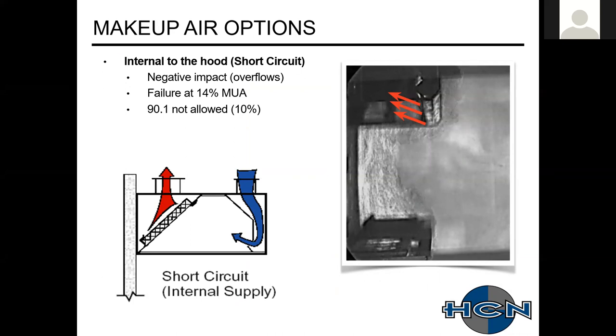The problem with this is, in the way the IMC and the code is written, they'd say your net, whatever you're bringing into the hood, you actually have to take out. So if you're doing 2000 CFM exhaust and you're bringing in 1800, the net exhaust is actually only 200 CFM. So if you're not even a listed hood manufacturer, you cannot produce these. Most listed manufacturers aren't even doing internal comps.